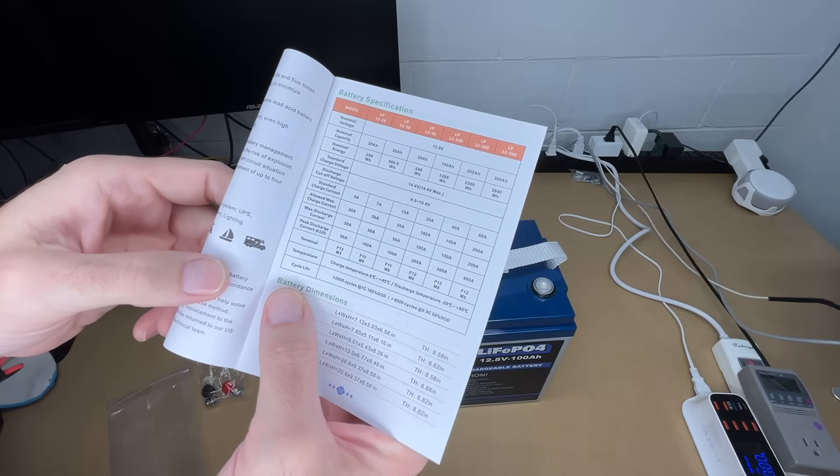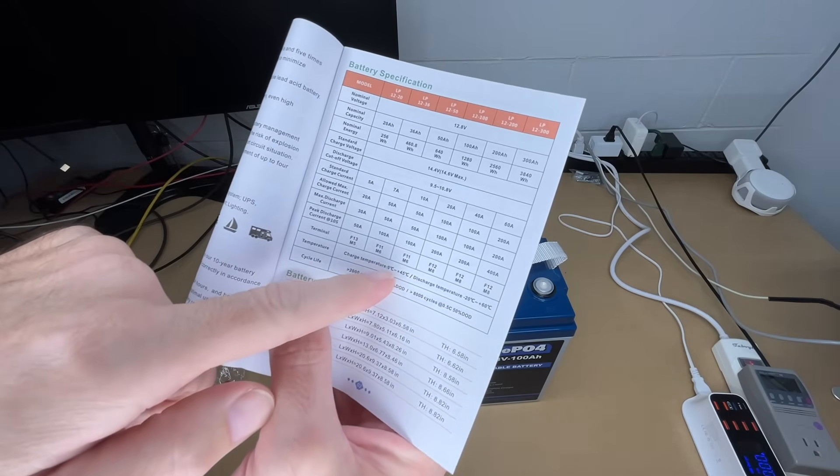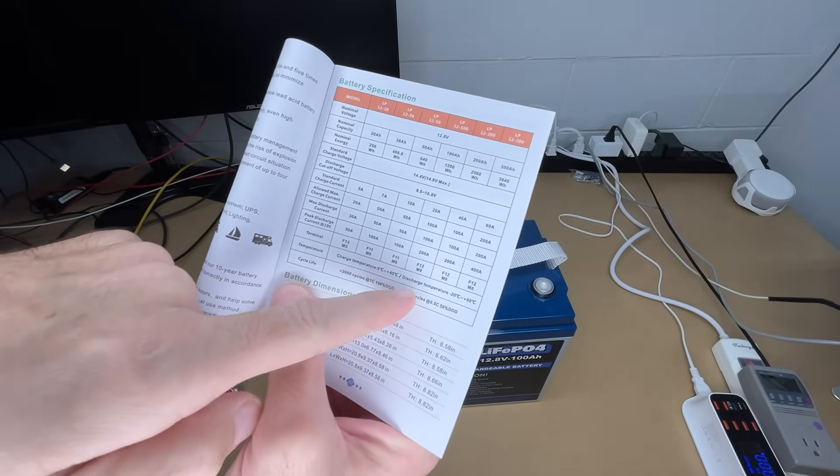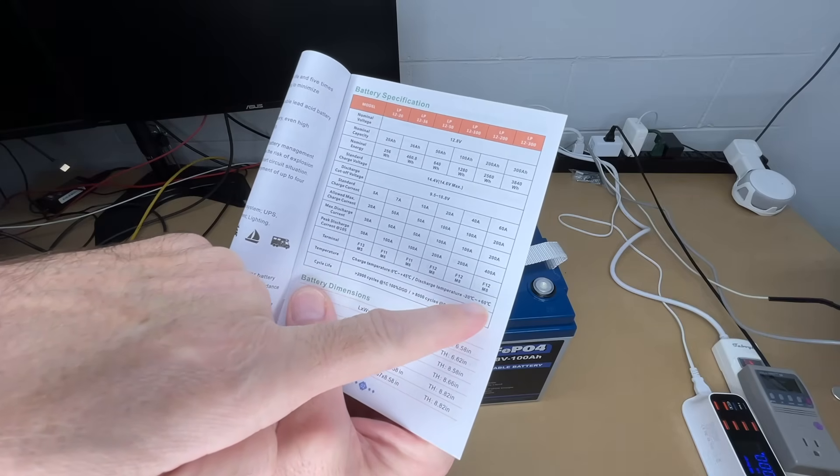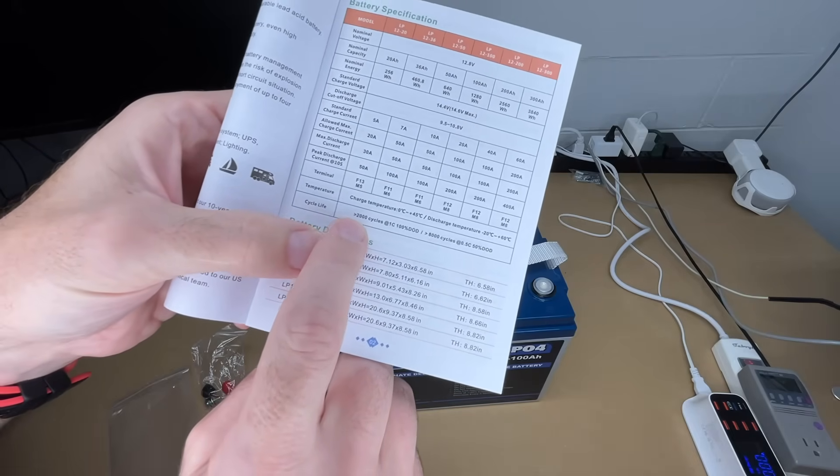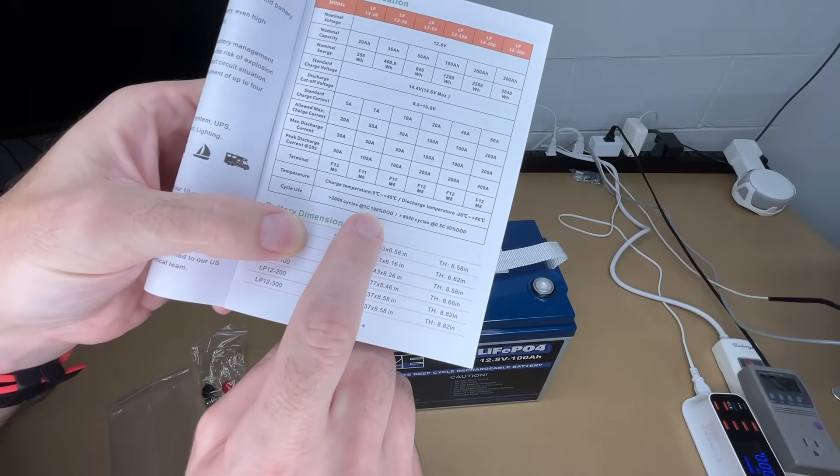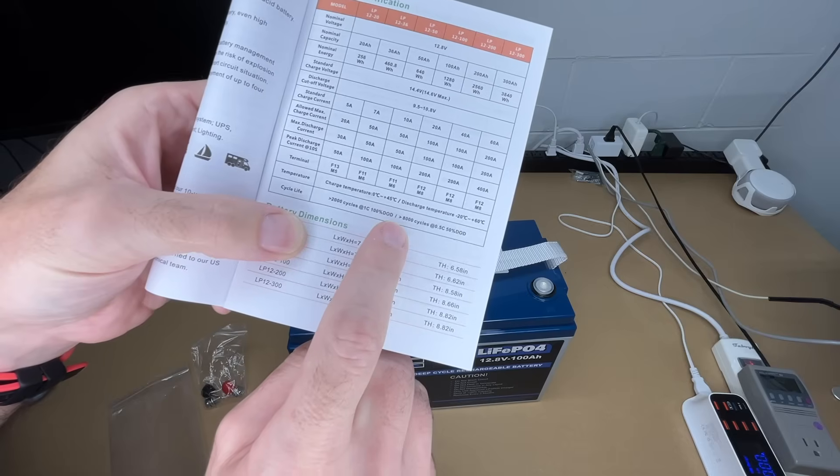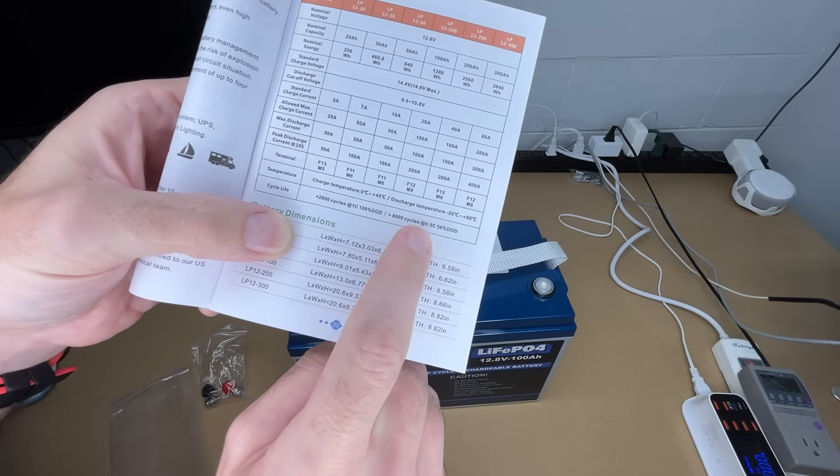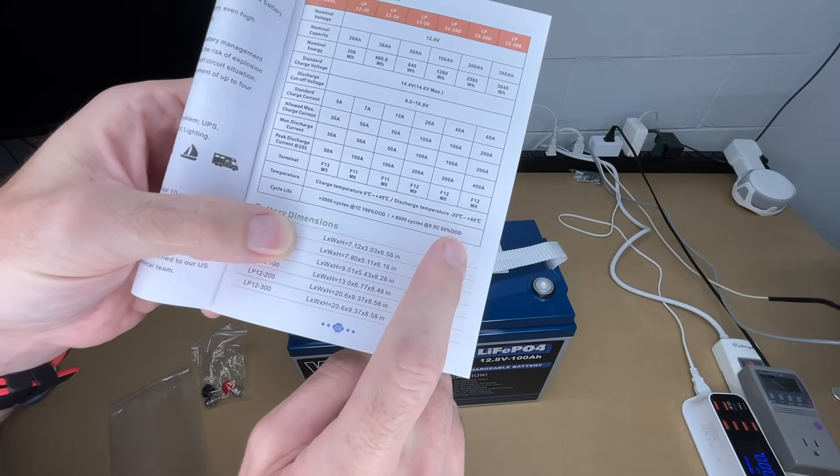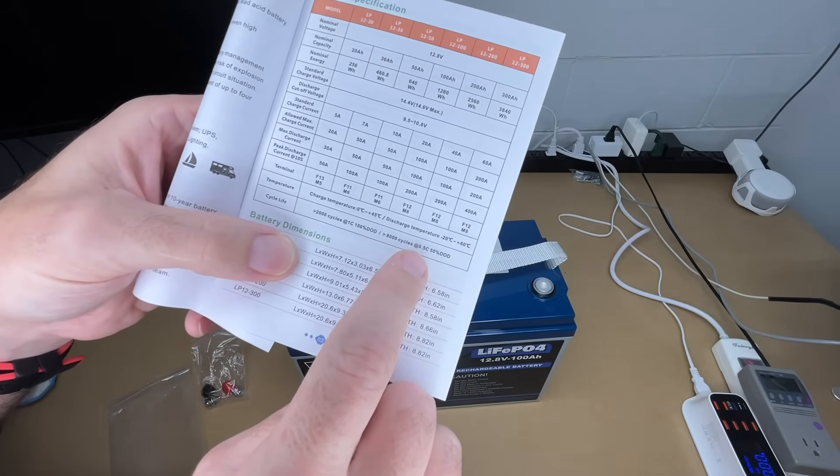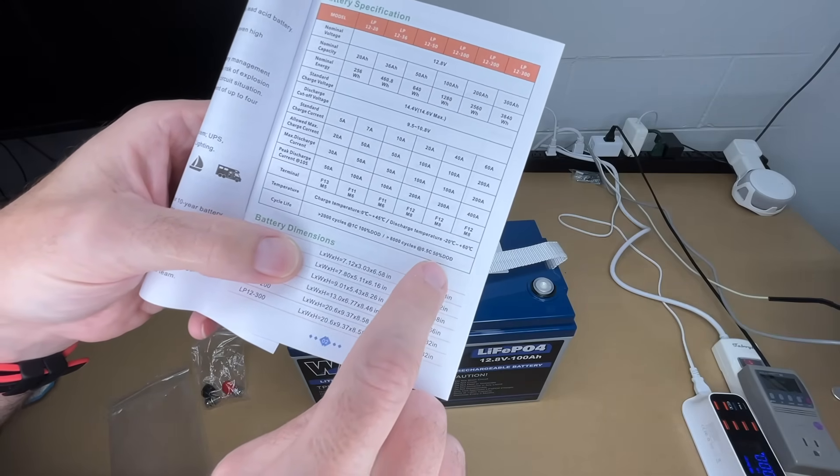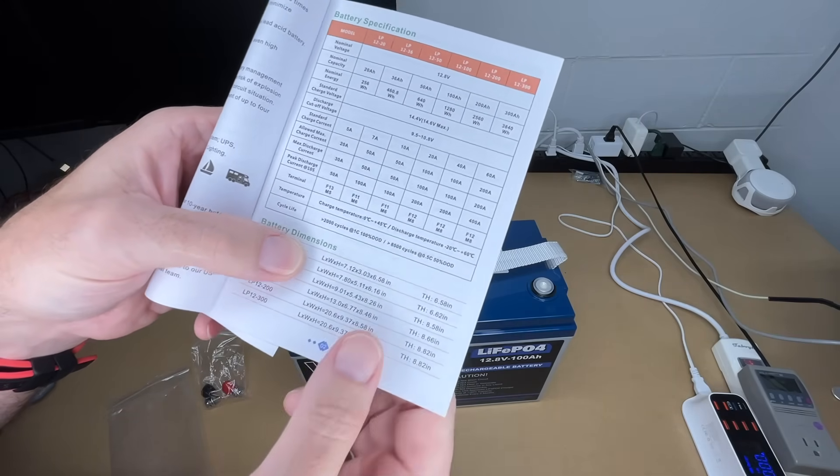Discharge temperature is -20 to 60 degrees Celsius. The cycle life on this is greater than 2,000 at 1C with 100% depth of discharge, and greater than 8,000 cycles at 0.5C with 50% depth of discharge. Essentially, what that's saying is if you discharge it slowly and you don't discharge it all the way, you'll get greater than 8,000 cycles.